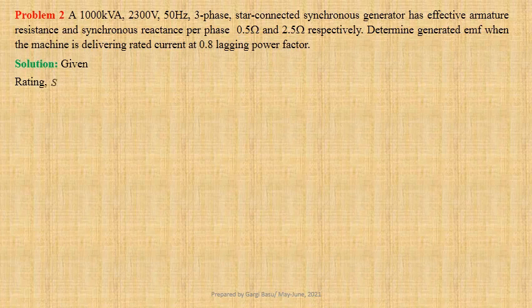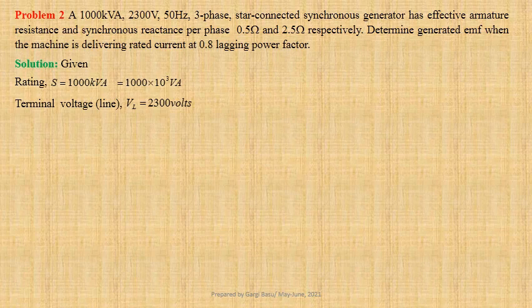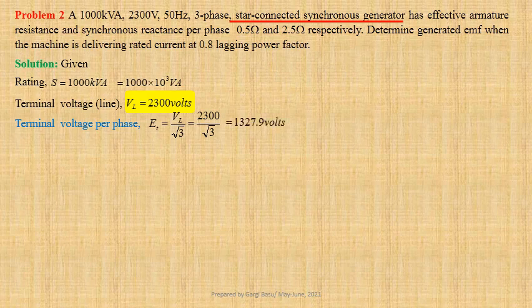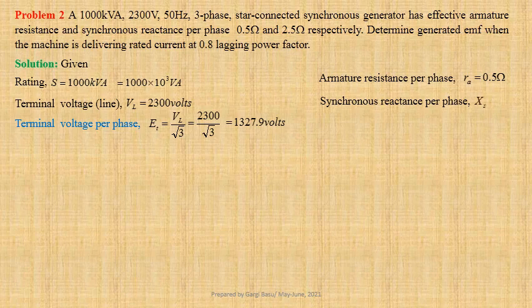Rating of the generator S equals 1000 kilovolt ampere. That is equal to 1000 into 10 to the power 3 volt ampere. Line to line terminal voltage VL equals 2300 volts. Since the armature is star connected, terminal voltage per phase ET equals VL by √3, that is equal to 2300 divided by √3, that gives us 1327.9 volts. Given armature resistance per phase RA equals 0.5 ohm. Synchronous reactance per phase XS equals 2.5 ohm. Load power factor cos phi equals 0.8 lagging.